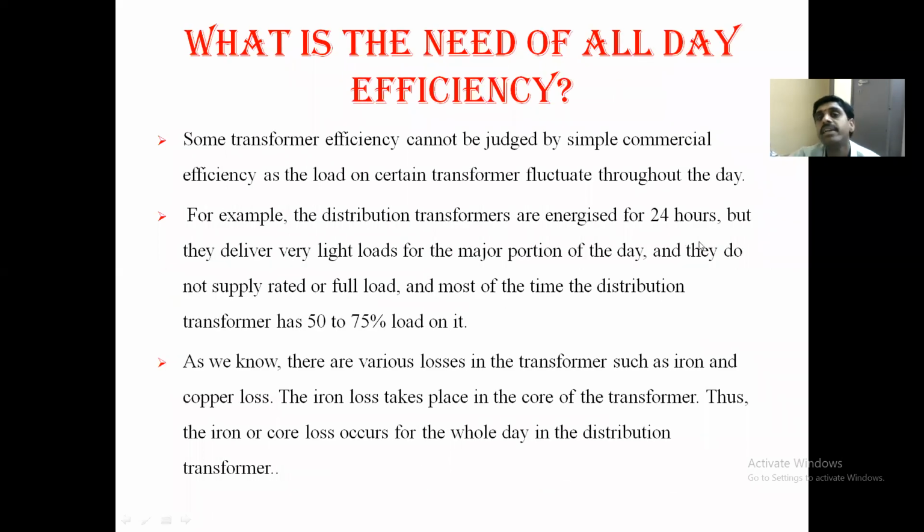So what is the need of this all day efficiency? Some transformers' efficiency cannot be judged by simple commercial efficiency on the load, as the load on certain transformers fluctuates throughout the day. Normally, if you take overall output and overall input, that won't serve the purpose. If you know hour to hour how the load is changing, that is important for calculation of the losses, as well as that gives the clear picture of the efficiency of a transformer.